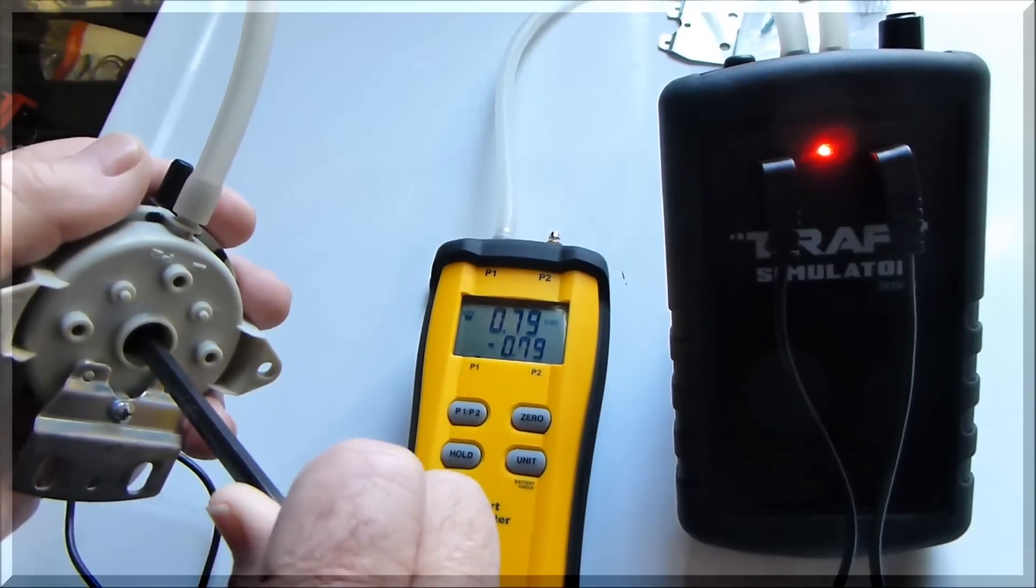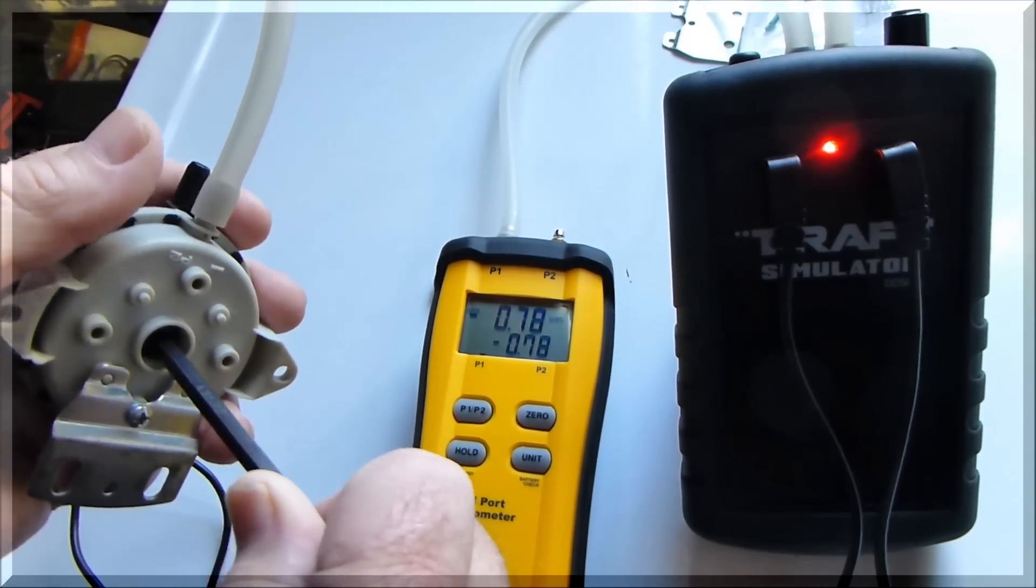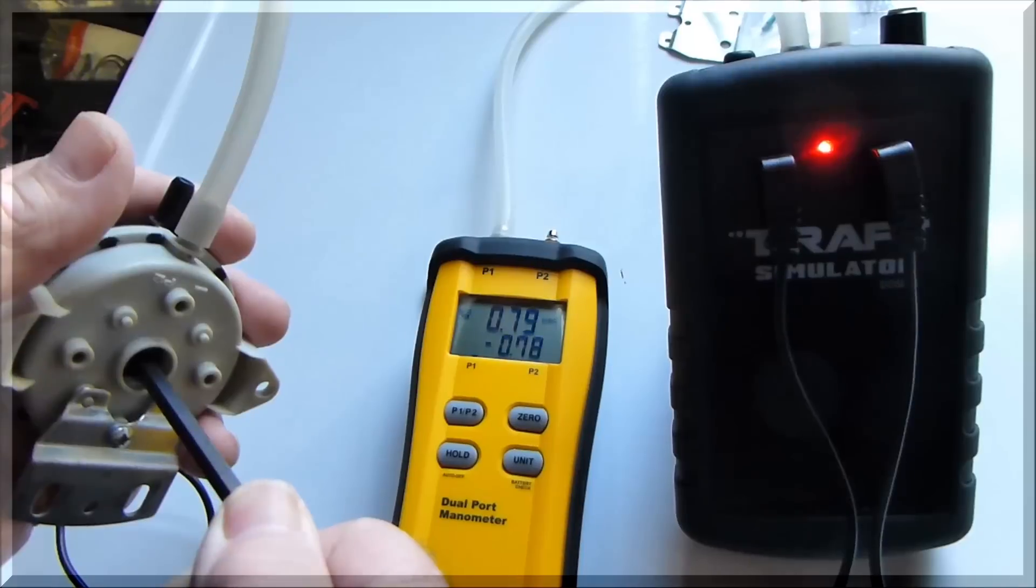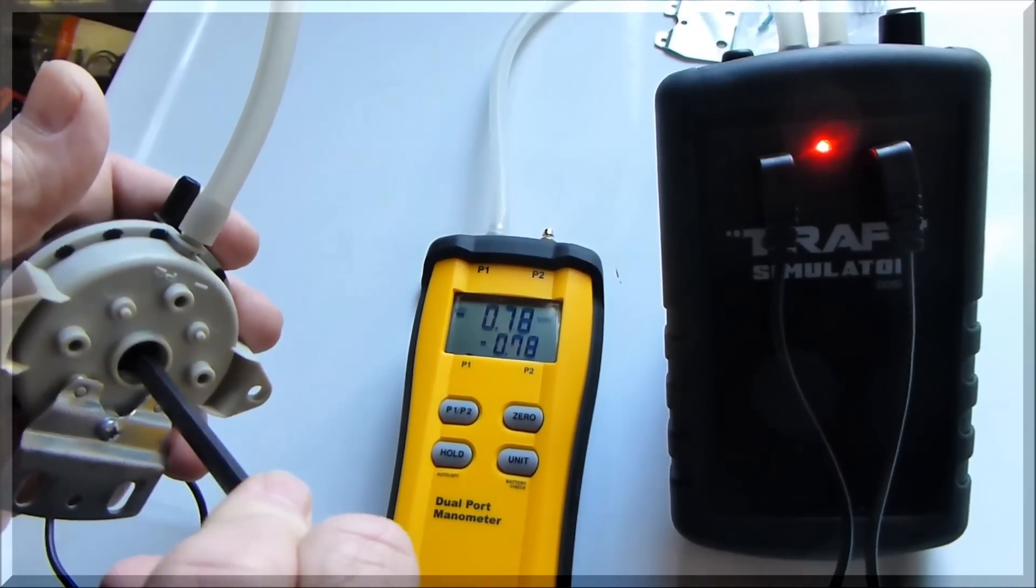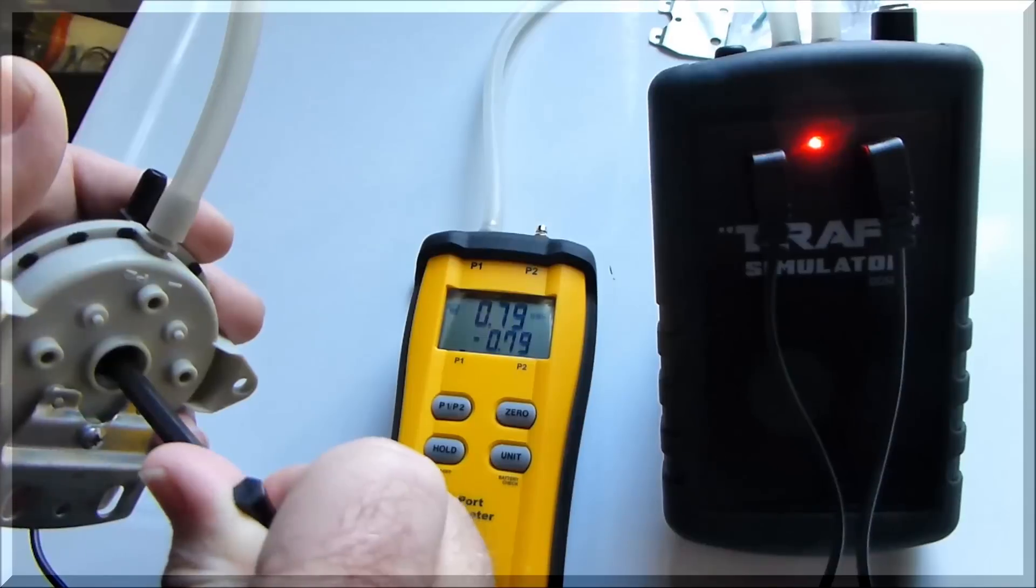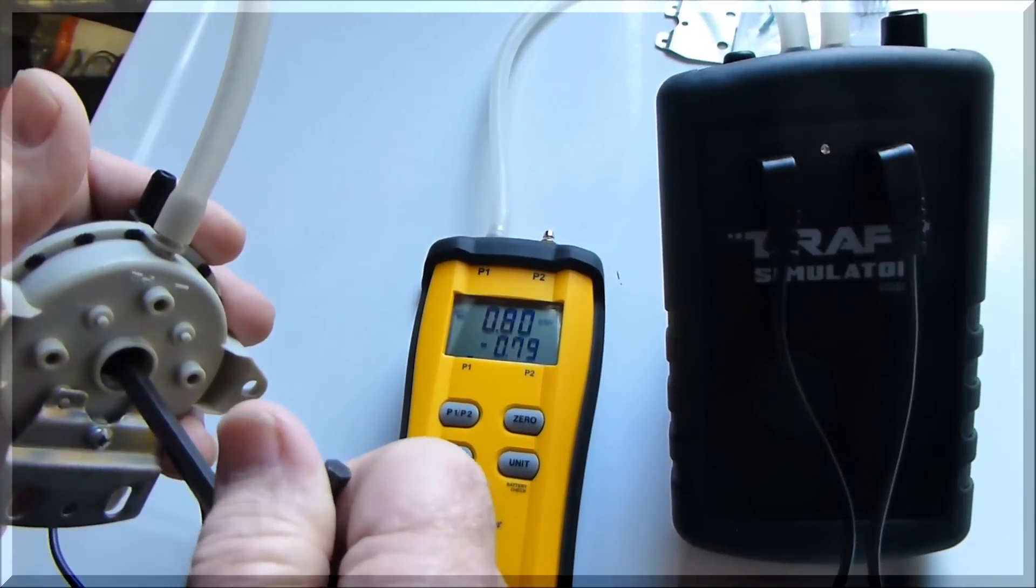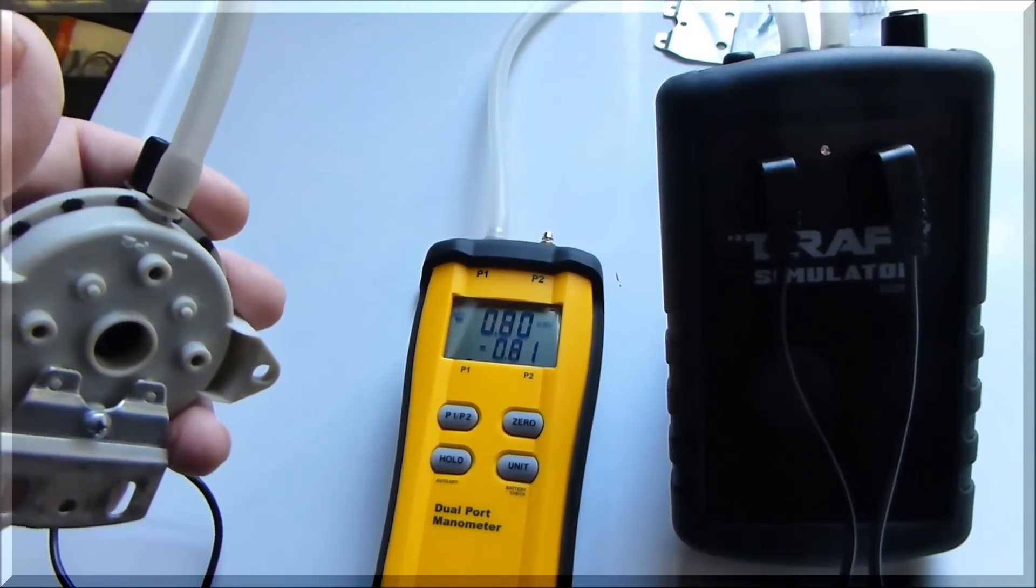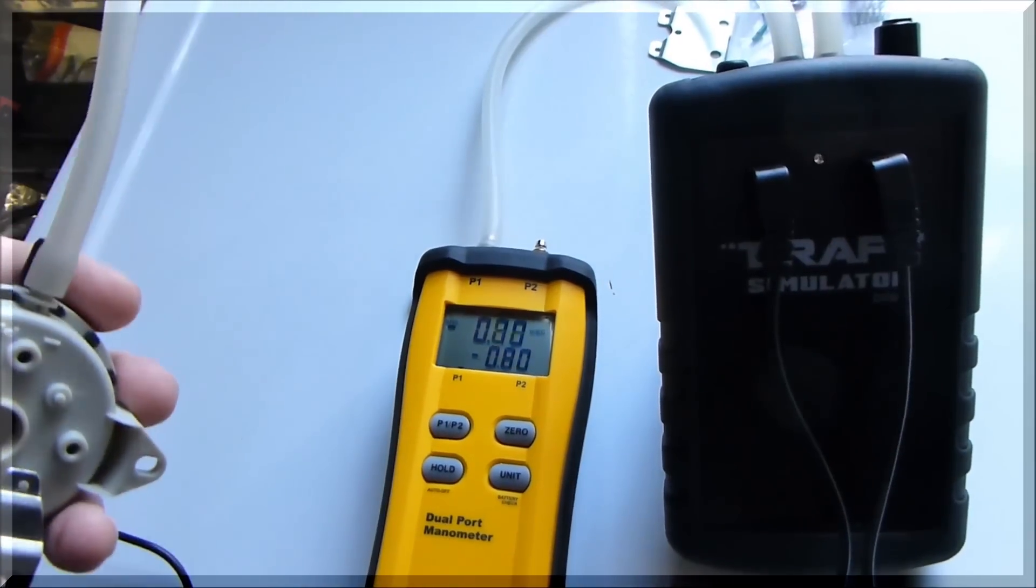We're going to adjust the adjustment screw until the LED on the DDSM1 turns off. And there we have it. We have a .80 inches of water column pressure switch.